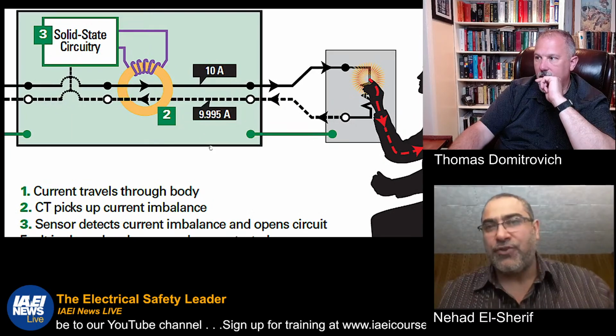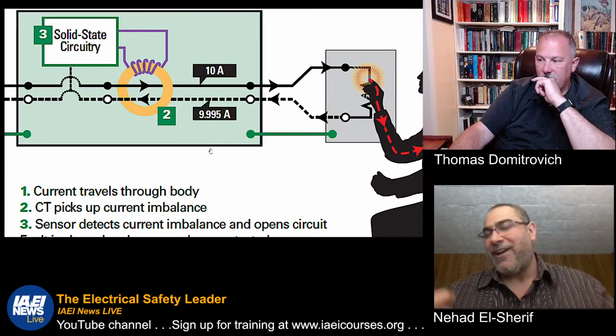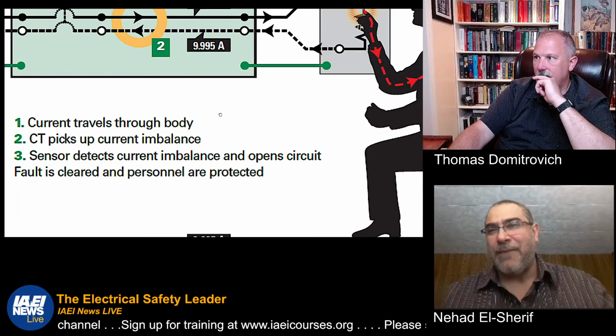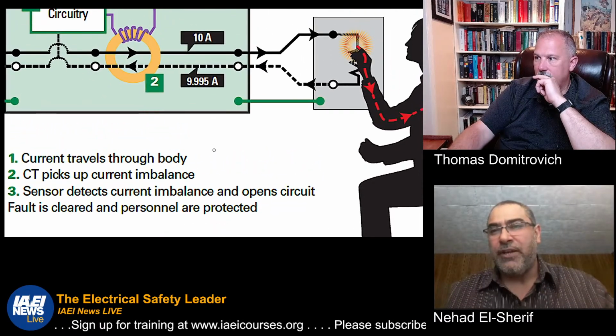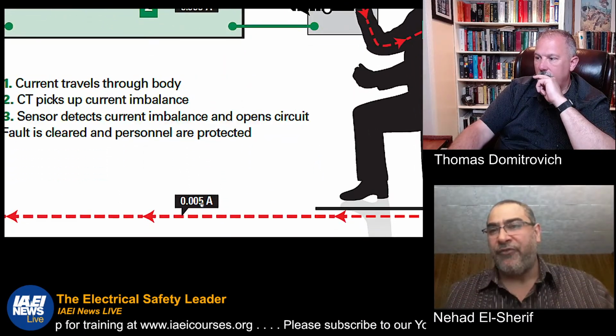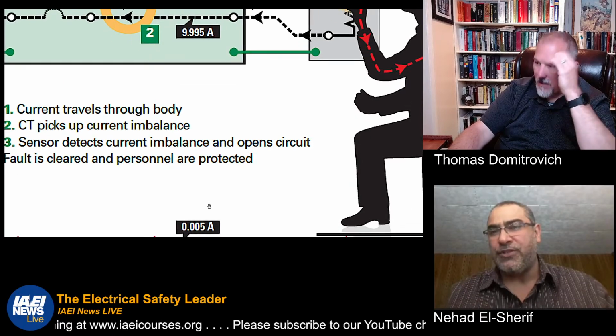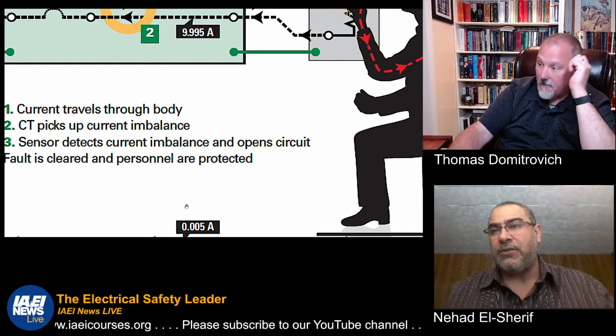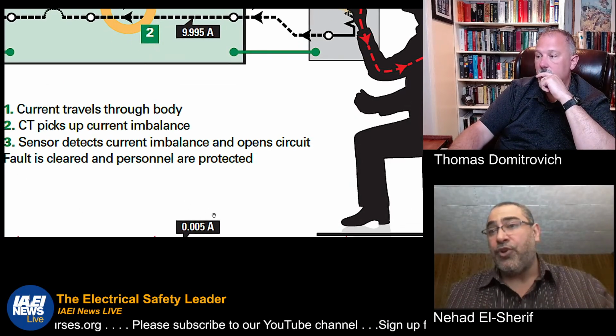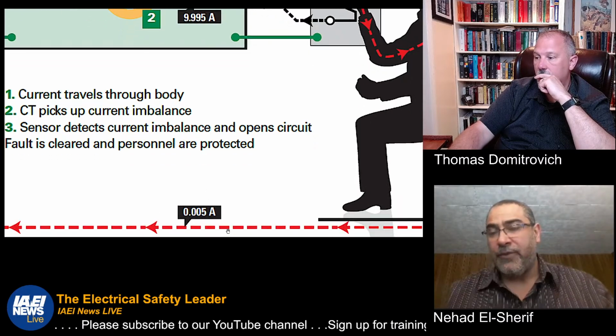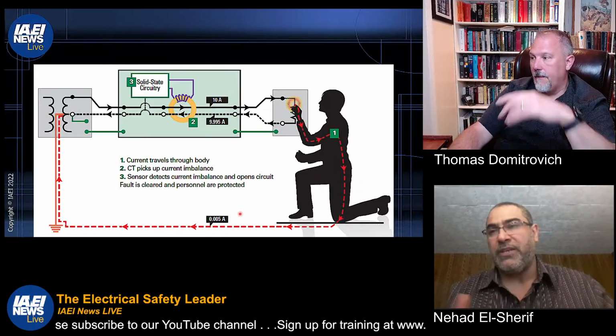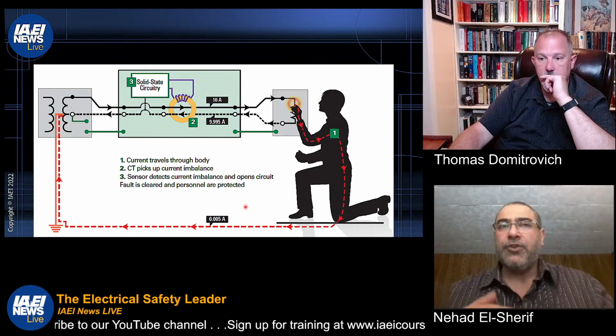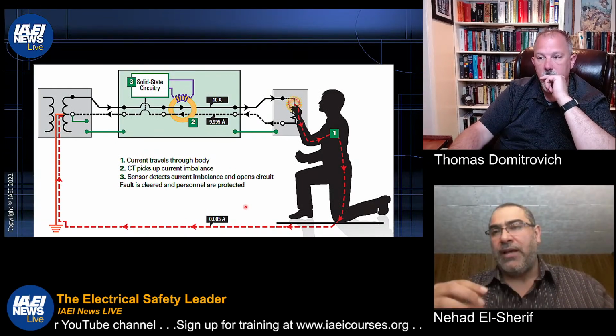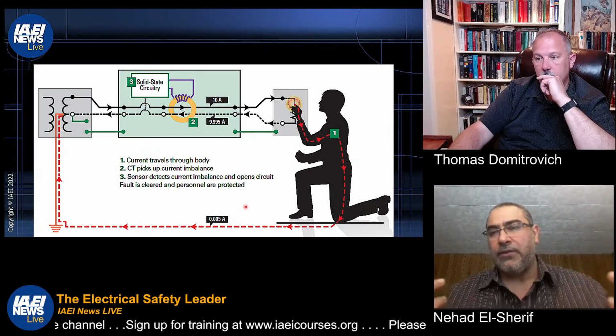Yeah, thank you, Tom. So you have 10 amperes going one way, but then the return is only 9.995. The difference is 5 milliamps, 0.005 amperes. This amount is returning to the source through a different path, which happens to be this person, which could be a shock hazard. So at the end of the day, this applies to people and equipment.